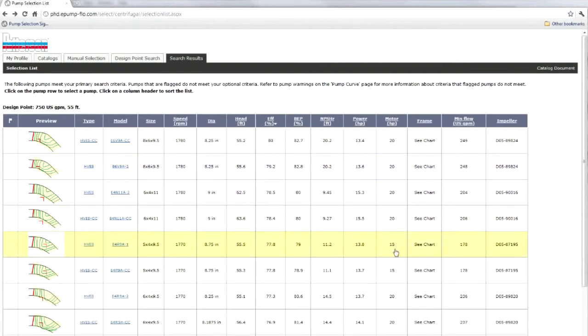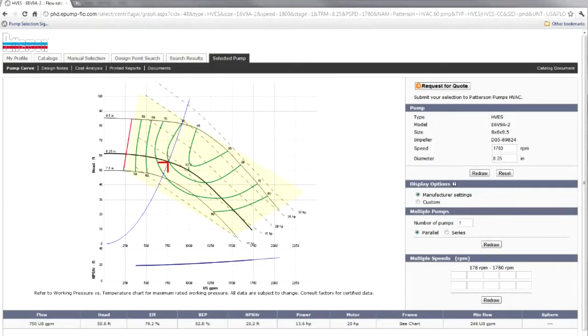Let's understand why. Let's look at the curve for the larger pump. If we look at the brake horsepower, or try to estimate what the brake horsepower is with this pump, we're sitting just under 15. So I could get away with the 15 horsepower. But when I hit approximately 900 gallons per minute, then I'm going to start to overload that 15 horsepower motor. Now, as I continue down my pump curve, at the very end of my pump curve, I'm actually back under 15 horsepower. But an engineer might look at this and say, well, I don't want to overload that 15 horsepower motor, so I'm going to put 20 horsepower on there.